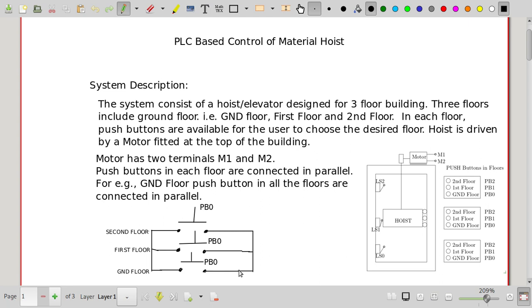The motor has two terminals, M1 and M2. For moving the motor up, M1 has to be positive and M2 should be negative. For moving the motor down, the polarity is reversed — M2 should be positive and M1 should be negative. Our connection and circuit should achieve both upward and downward movement of the hoist. The sequence of operation is simple: wherever the hoist is, if any push button is pressed, the lift moves toward the corresponding floor and stops when the corresponding limit switch is reached.